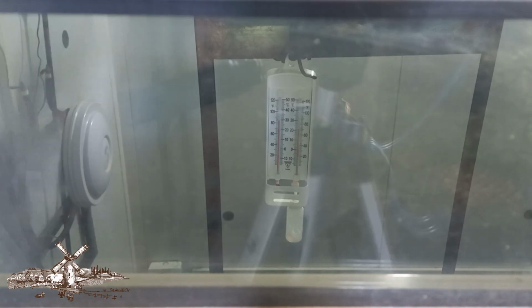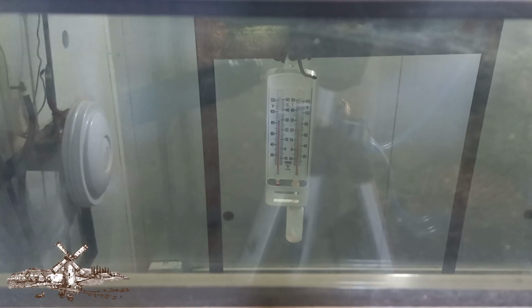Now, a lot of people ask me, can we use a digital thermometer hygrometer which they bought online, or a data logger? And my answer to you would be no. The reason is because your data logger and your thermometer hygrometer are made of the same components as your controller. And so they have very much the same problems. And so not only do you have to calibrate your incubator controller, but if you intend on using your thermometer hygrometer and your data logger in your incubator, you have to recalibrate those as well.